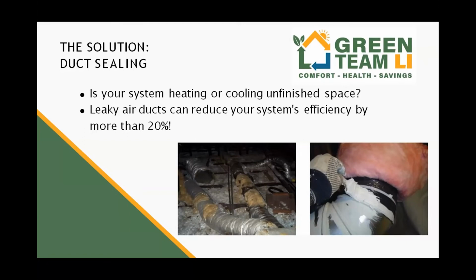If we lose 10% of the air leaking out through seams and penetrations of the ductwork, still that's not bad. 90% in school is a pretty good grade. So if 90% of the air goes through to where it needs to go, that doesn't seem so bad. But in fact, that's a lot of leakage. Could be dropping 10, 15, even 20% off of the efficiency of the overall system.